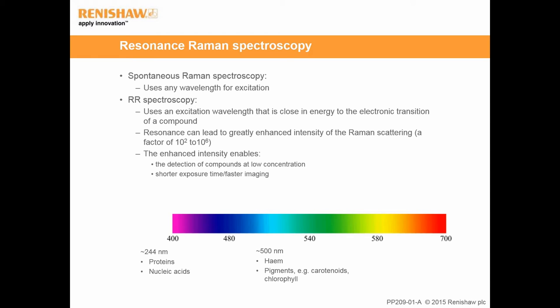We can use light of any particular wavelength to excite samples in spontaneous Raman spectroscopy. Resonance conditions are achieved when an excitation wavelength close in energy to the electronic transition of a compound is used. Resonance can lead to greatly enhanced intensities of Raman scattering, up to a million times. This resonance enhancement enables compounds to be detected at low concentrations, and short exposure times can be used for faster imaging. Deep UV wavelengths at around 244 nm can be used for resonance Raman spectroscopy of proteins and nucleic acids. Visible wavelengths at around 488 to 532 nm can be used for heme and pigments such as carotenoids and chlorophyll.